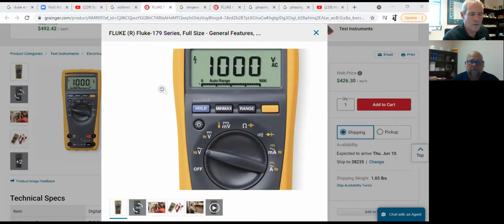I saw a guy one time take one lead in a small space. It was a small meter base, and he was trying to prop the meter up on the meter base. He took one lead and touched it to the energized wire coming into the meter. And guess where the other lead was? On his finger. He was holding it in his mouth. Okay guys, remember, difference of potential here. Your mouth and your feet on the ground is going to be the new path for current flow. That meter does the same thing. It's a conductor, so treat it as such.